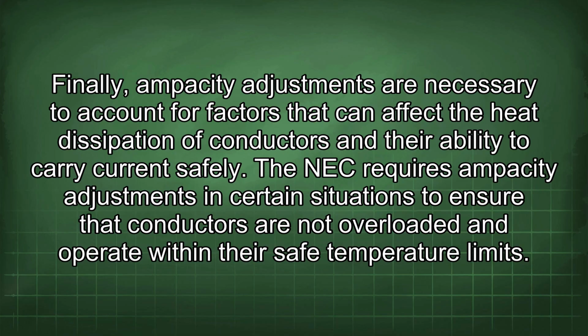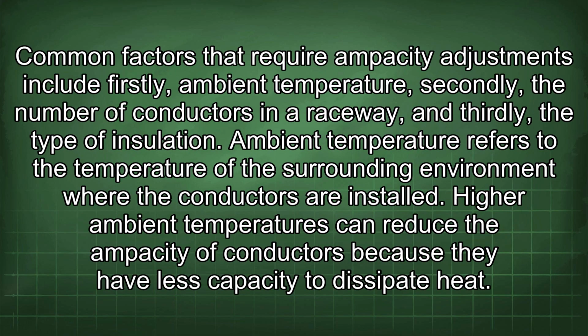Finally, ampacity adjustments are necessary to account for factors that can affect the heat dissipation of conductors and their ability to carry current safely. The NEC requires ampacity adjustments in certain situations to ensure that conductors are not overloaded and operate within their safe temperature limits.